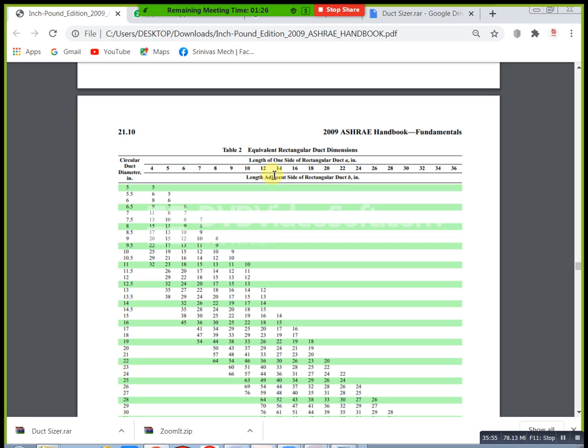See, okay, I will explain that one. See, this is our width. You got in the previous case, for example, 8 inch. This is how much? Height 14 inch. In this condition you need to connect your duct from this, our last duct. How can you connect? This is the right procedure. In the side condition you will get this as our height, this is our next duct, this is our height in the previous duct. This is wrong, this condition is wrong. This is our standard height, 14 inch. From the machine also we have the same height.